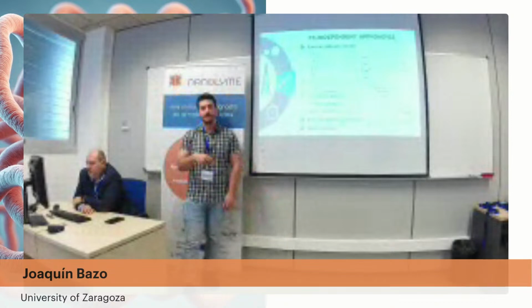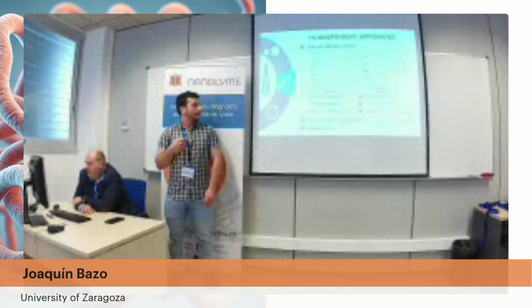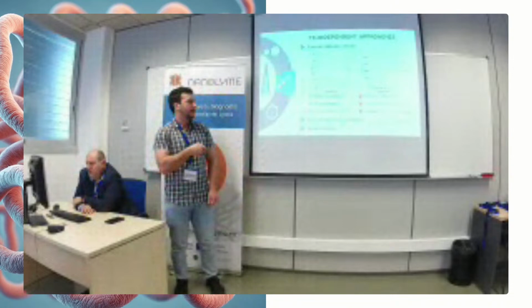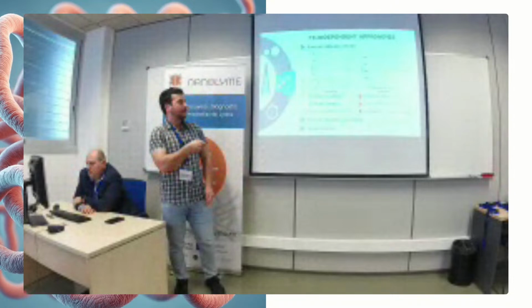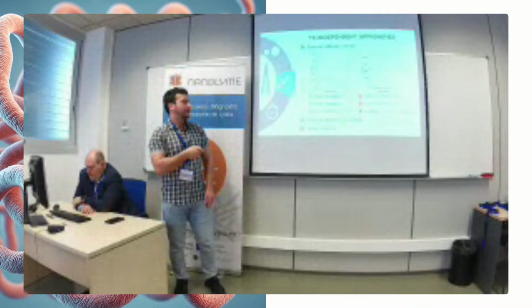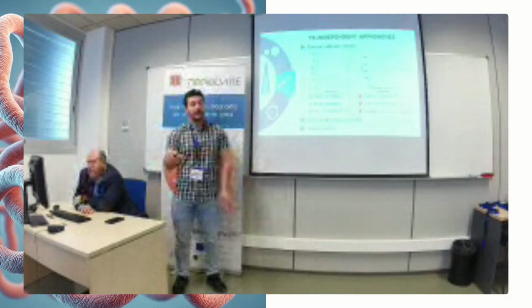So yeah, very simple. We don't require standards as in the previous methods, and the uncertainty is also very low. But it has some other issues. First, it's difficult to have nanoparticle standards well distributed around the curve. That means, especially here, that the bigger nanoparticles may govern the calibration on their own. So it may negatively impact the lower nanoparticles, obtaining significant errors.